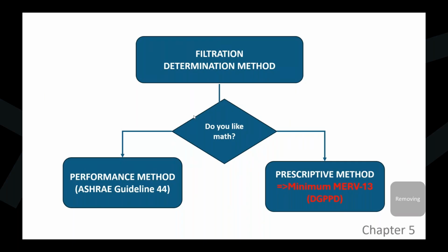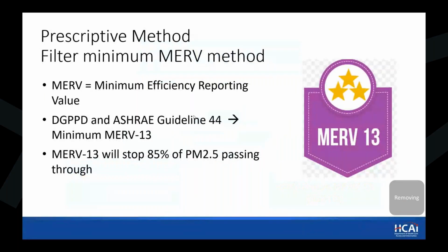Now, if you like math and you have an engineer who likes math, you can go to the performance method, which is outlined in Guideline 44. So the prescriptive is really just putting in MERV 13. MERV 13 will stop about 85% of PM 2.5, and that's on one pass. The more you circulate the air through the filter, the more you'll be able to stop the PM 2.5. And as I mentioned, MERV 13, especially if you are designing an acute care hospital, should be attainable. Even for other buildings, with all the parking requirements, I see it as a very doable, very reachable MERV rating.